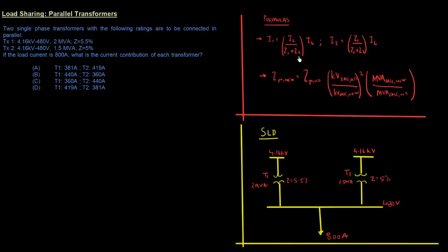The first formula relates the load current to the current contribution from each of two parallel transformers — we'll derive this shortly. The second formula involves the per-unit method, where we convert an impedance from one base to another — from an old MVA and voltage base to a new one. I'll explain this when we reach that step.